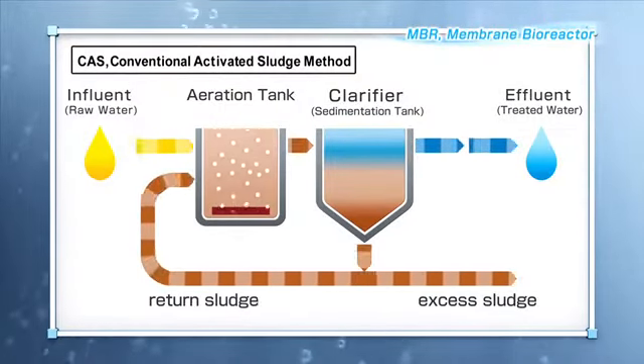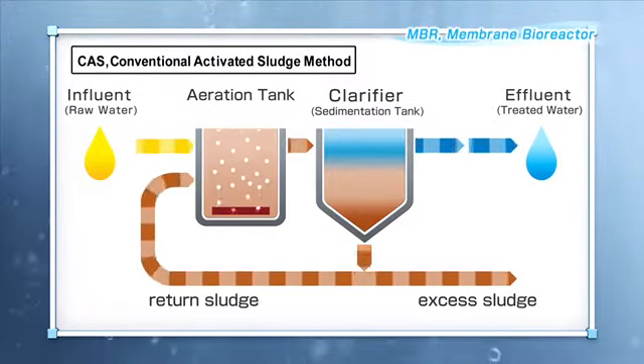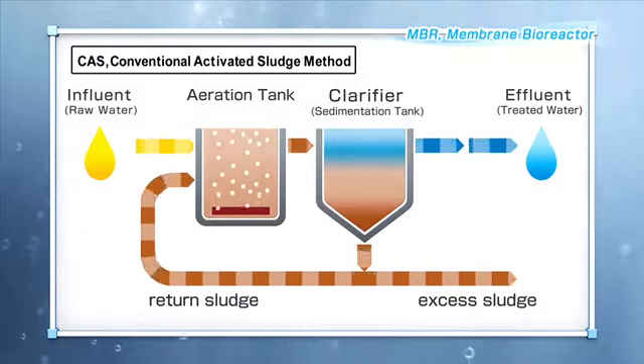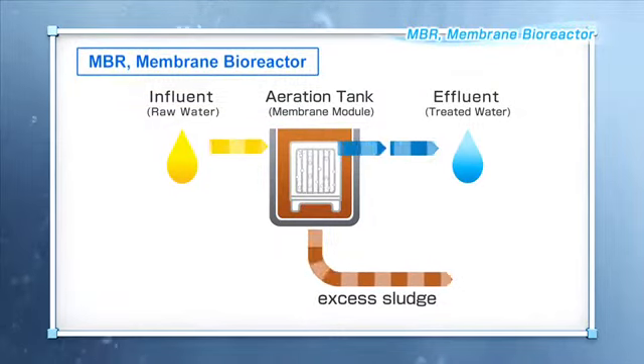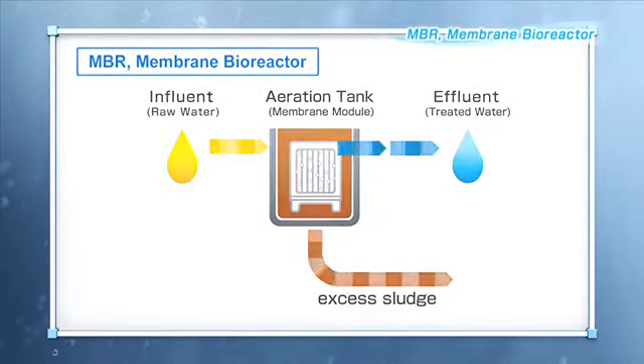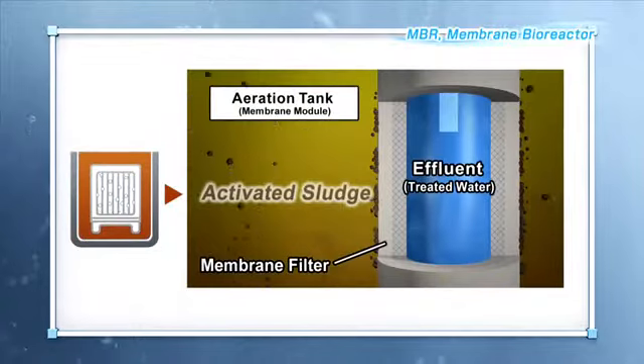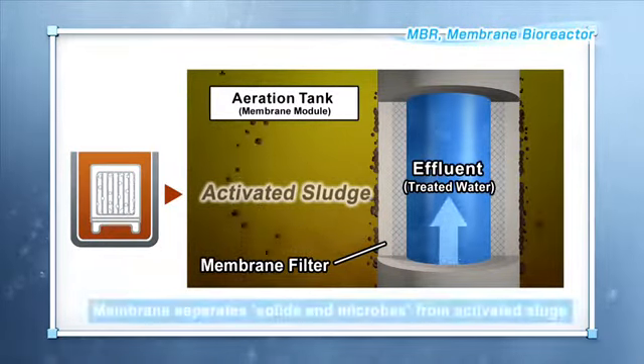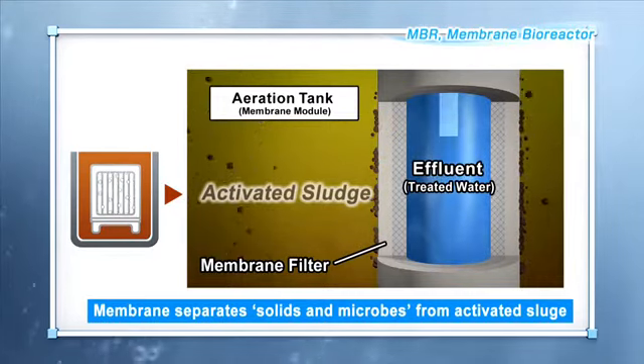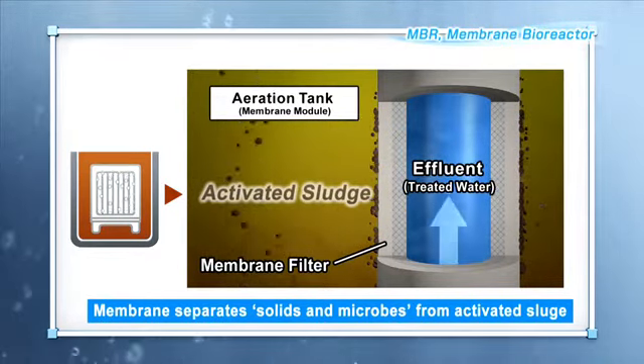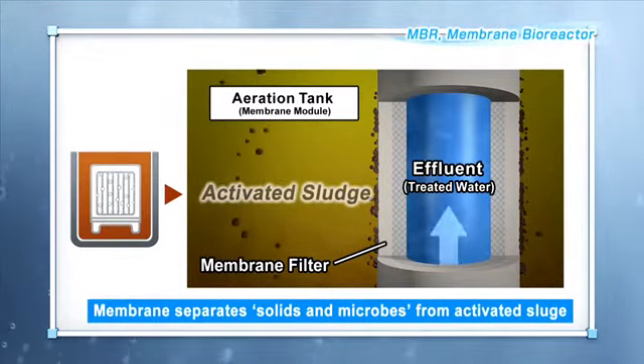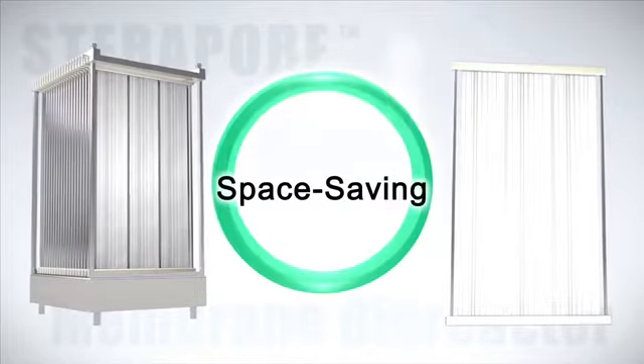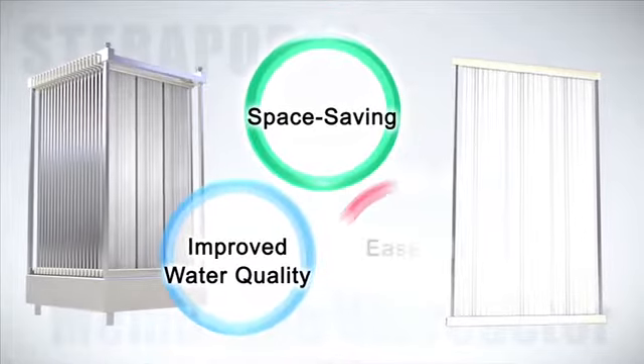In the conventional activated sludge method, sludge is separated into solids and liquids in a settling tank — this is called clarification. On the other hand, MBR separates activated sludge using a membrane module. MBR has a high level of water treatment capability, and combines membrane modules with the activated sludge method, making possible the recycling of water.